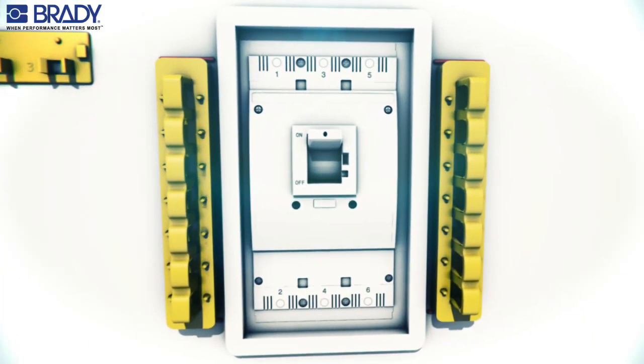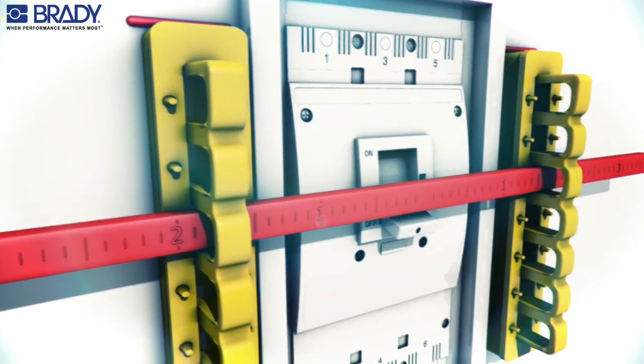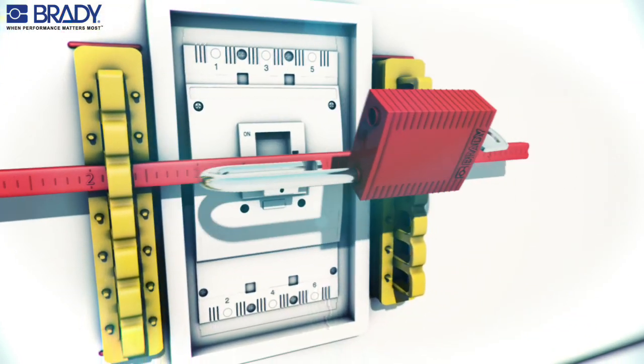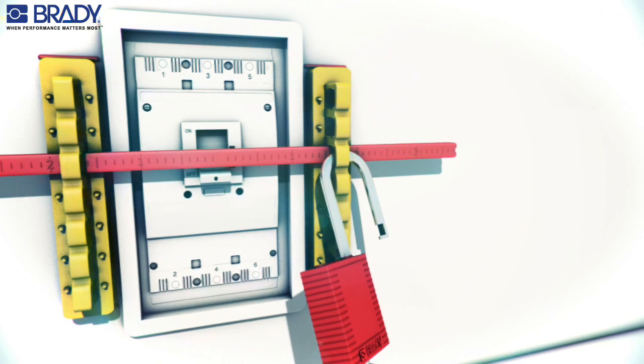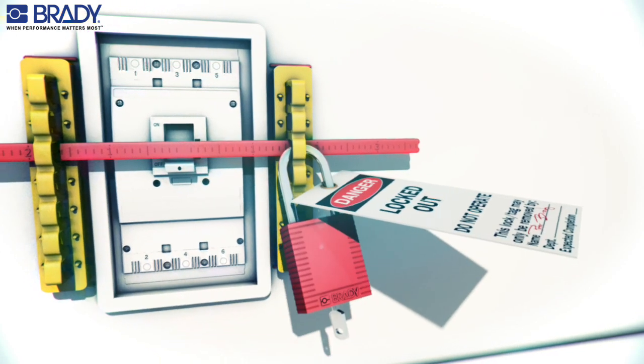To block the switch in the off position, place the red blocking bar. Insert a padlock with a tag in one of the yellow bars at the red bar level.